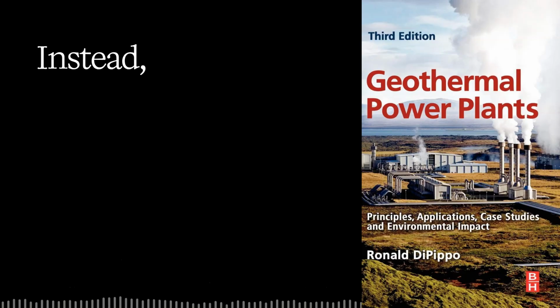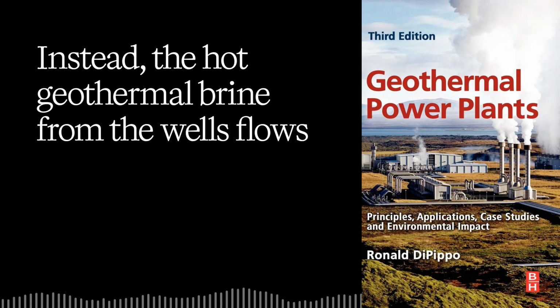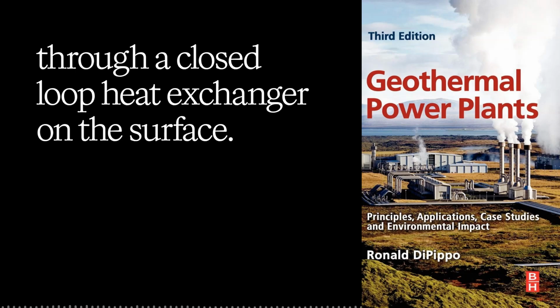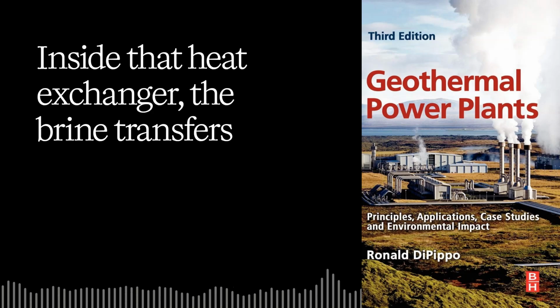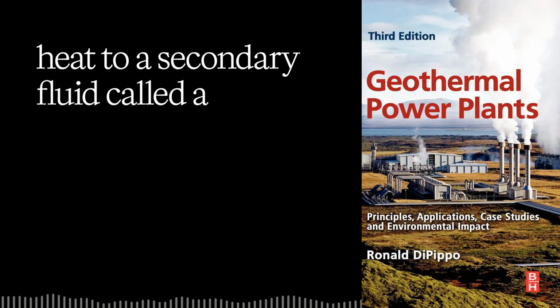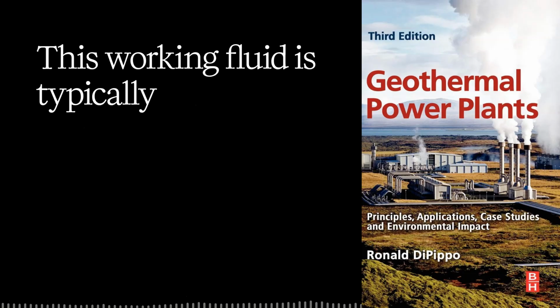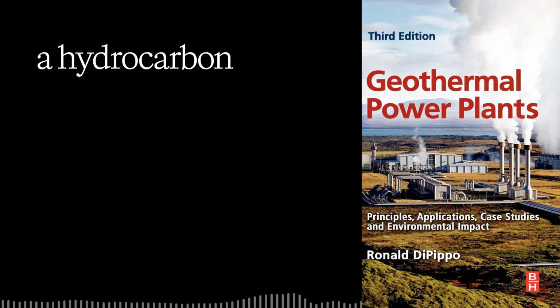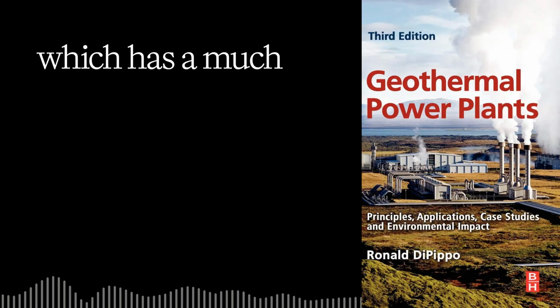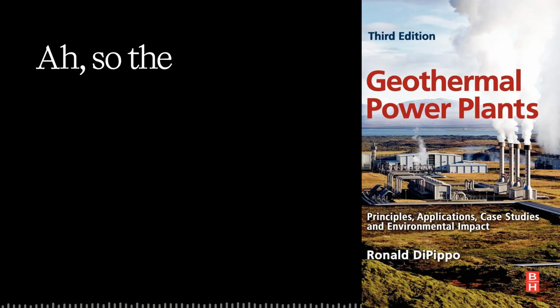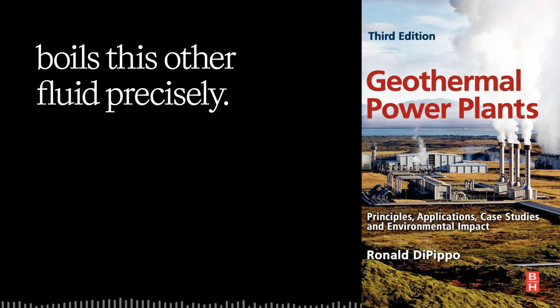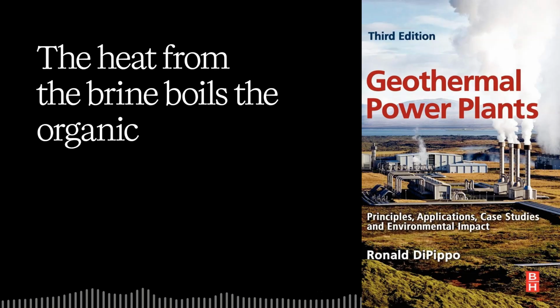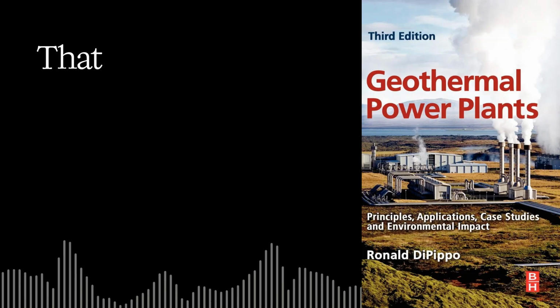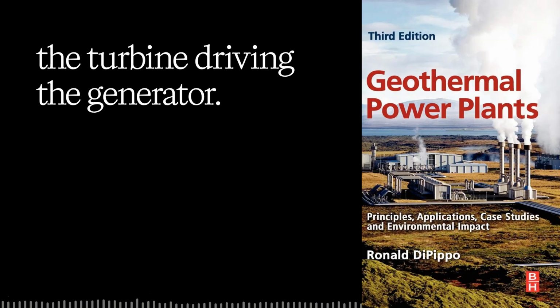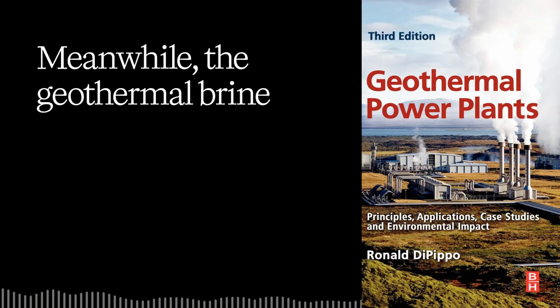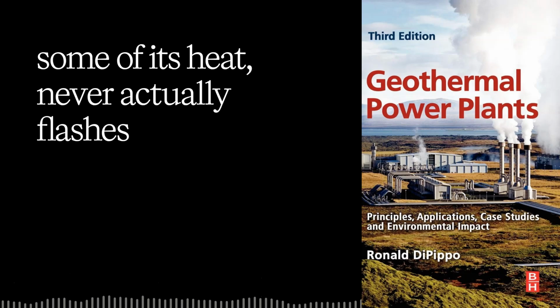No, they don't. Instead, the hot geothermal brine from the wells flows through a closed-loop heat exchanger on the surface. Inside that heat exchanger, the brine transfers its heat to a secondary fluid called a working fluid. This working fluid is typically an organic compound, often a hydrocarbon like isopentane or isobutane, which has a much lower boiling point than water. So the geothermal brine boils this other fluid. Precisely. The heat from the brine boils the organic working fluid into a high-pressure vapor. That vapor then expands through the turbine, driving the generator. Meanwhile, the geothermal brine, having given up some of its heat, never actually flashes or boils itself.